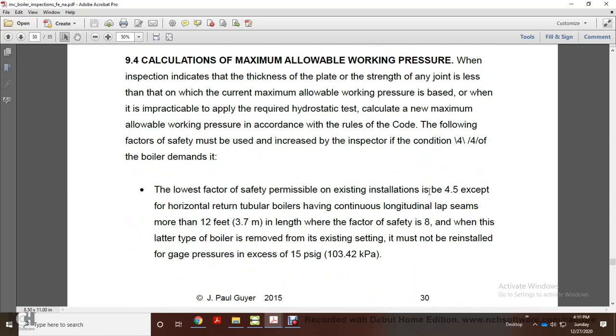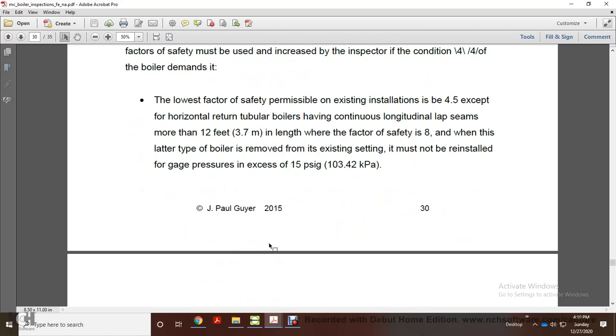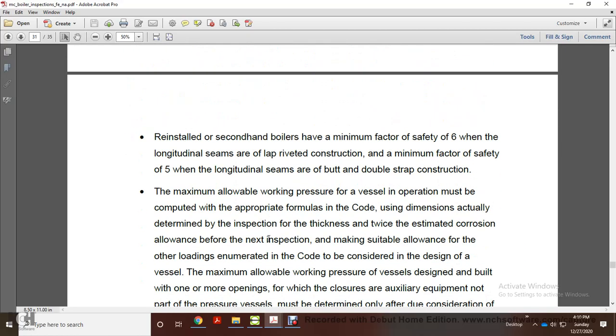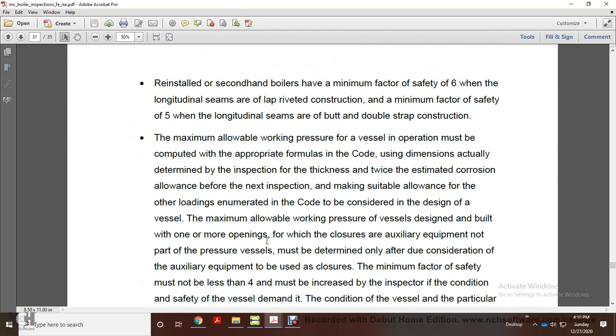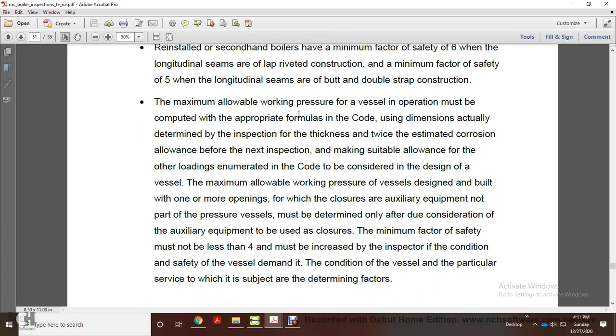The lowest factors of safety permissible for existing installations: 4.5 for horizontal return tubular boilers with continuous longitudinal lap seams more than 12 feet in length, the factor of safety is 8. When a boiler of the latter type is removed from its existing setting, it must not be reinstalled with a gauge pressure in excess of 15 psi gauge. Reinstall a secondhand boiler with a minimum factor of safety of 6 when the longitudinal seams are lap riveted construction, and a minimum factor of safety of 5 when the longitudinal seams are butt and double strap construction.